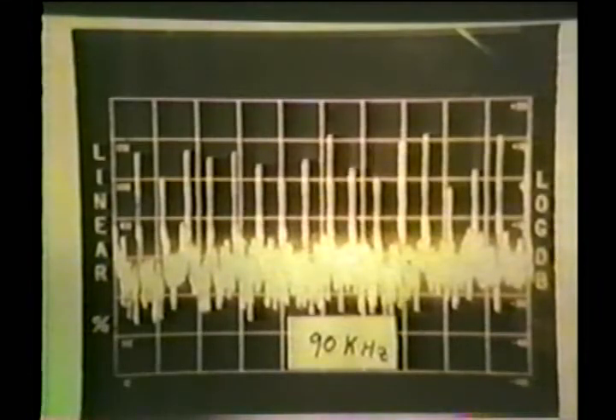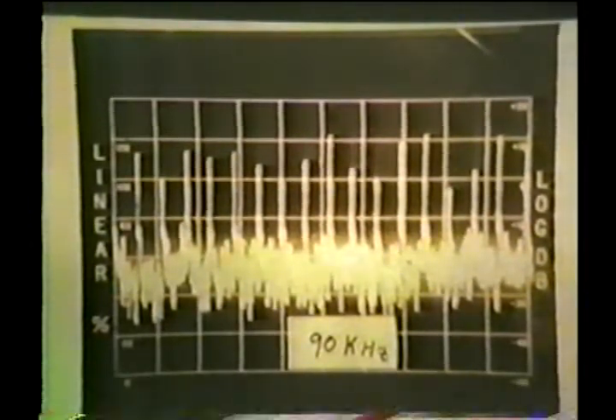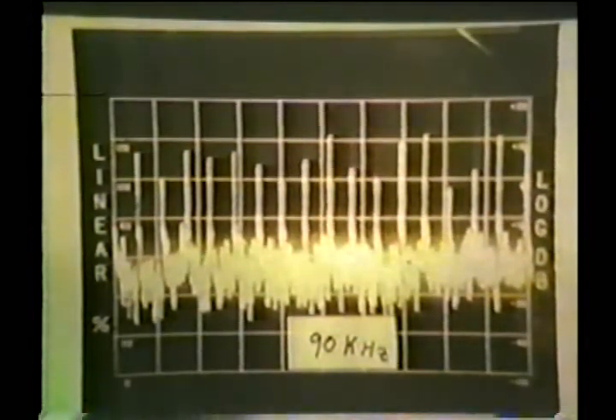Another type of EMI are gap discharges. Again, they're frequency selective. This picture was taken at 90 kilohertz. The pattern is not necessarily in synchronism with the power frequency. Much fewer discharges are present, as was with microsparking, because these are discharges taking place across relatively large gaps. The pattern is not as repetitious as microsparking because each discharge is actually chewing away the insulation or destroying the slot conductive paint on the stator bars.